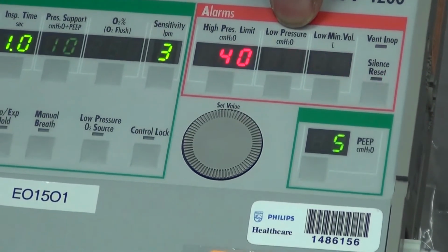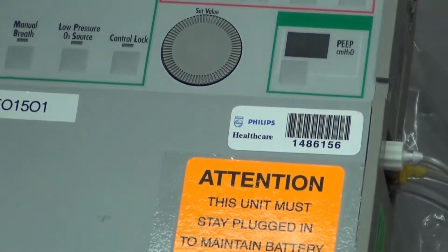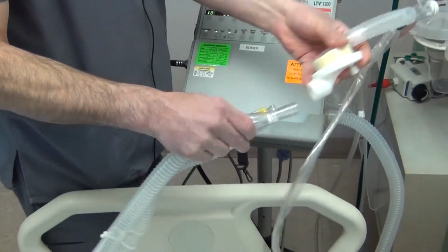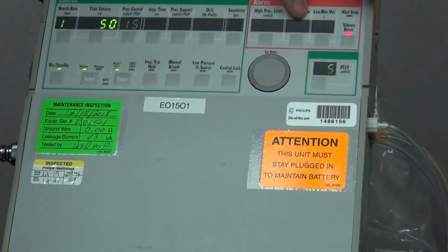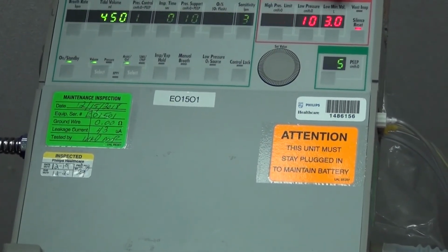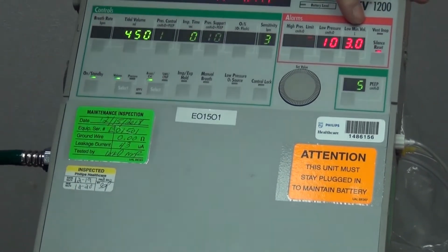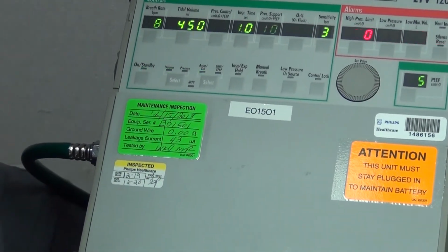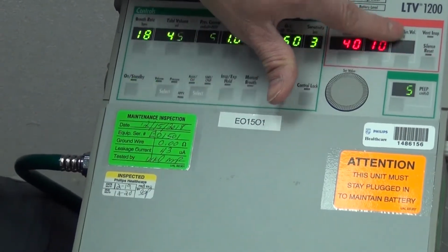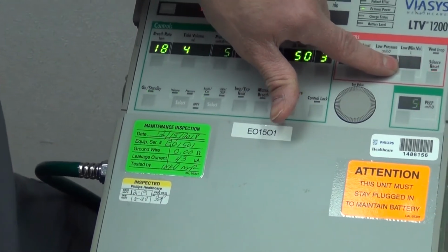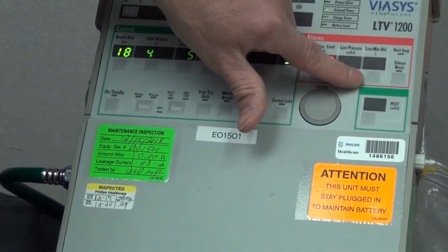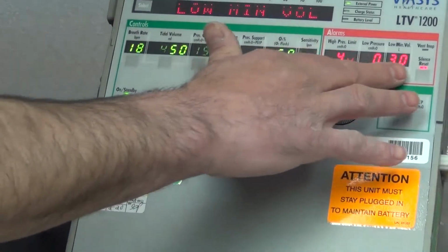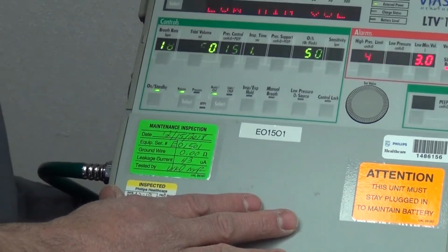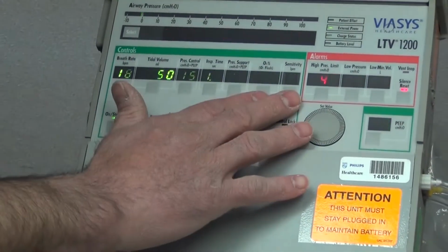The next one is a low pressure, meaning if the patient were to get disconnected from the ventilator for some reason, whether it's at the patient, at the ET tube, somewhere in the circuit, the machine would alarm. So you want that set. So this right now, it's set at 10 centimeters of water, which is a good setting. The next one is low minute volume or low minute ventilation. And that was set from 3 to 18 on the other machine, 18 being the high number and 3 being the low number. This machine only has the low number on it. So to start at 3 or 4 would be appropriate, depending on the patient's size, but a good cookie cutter beginning setting would be 3.